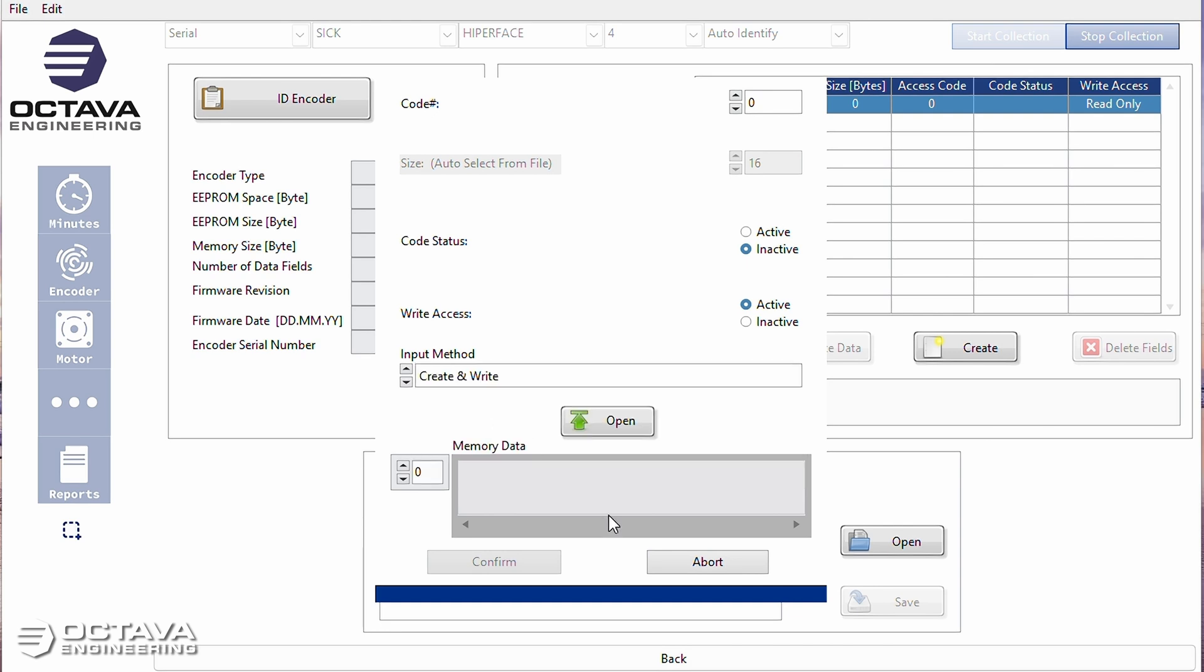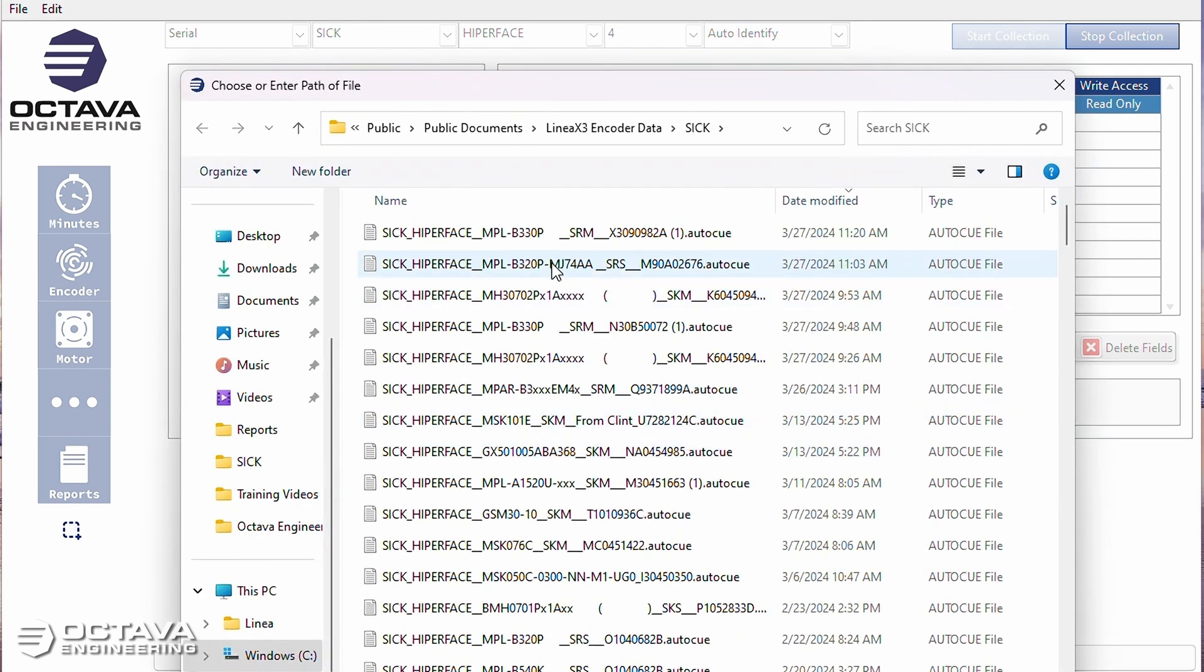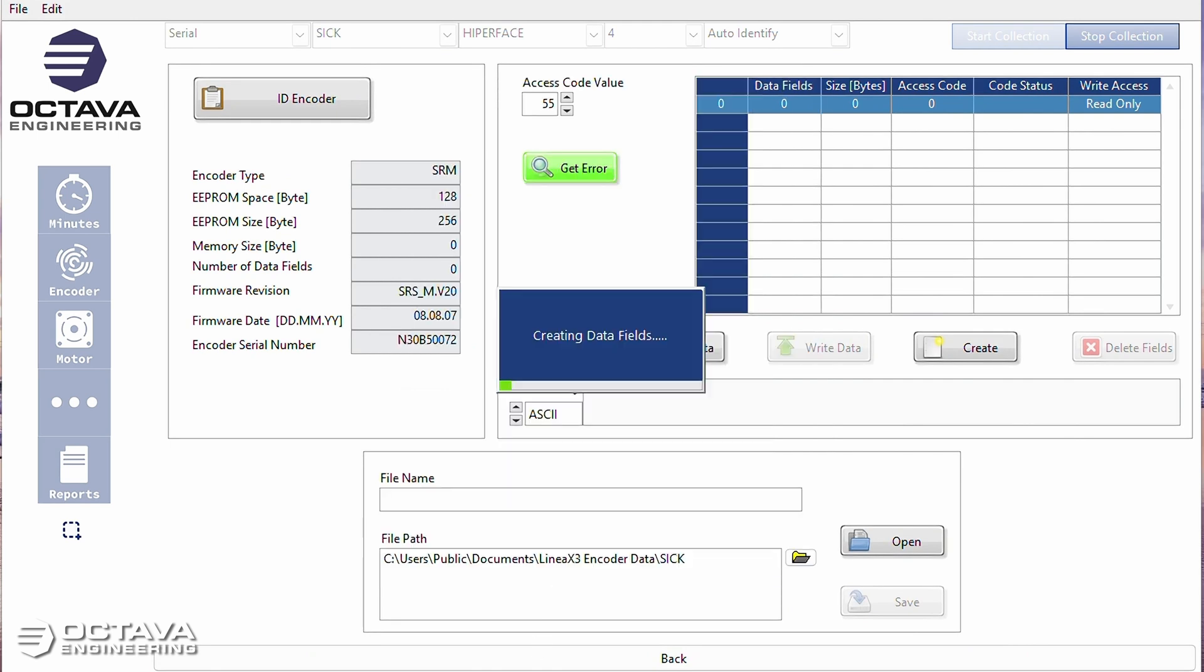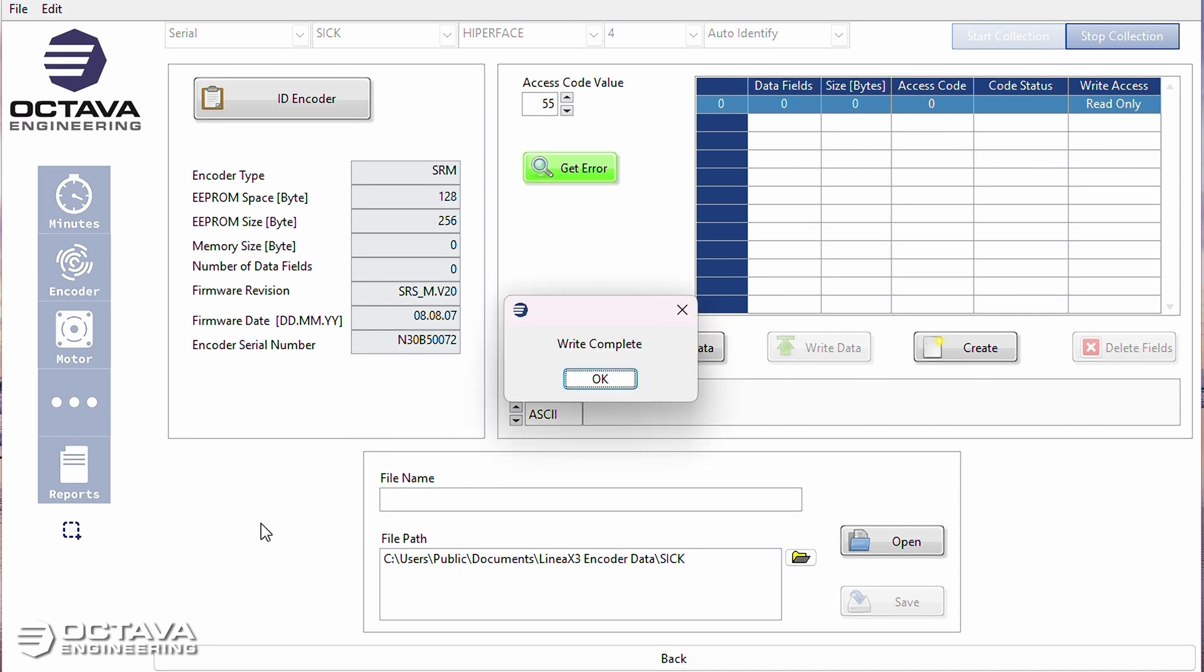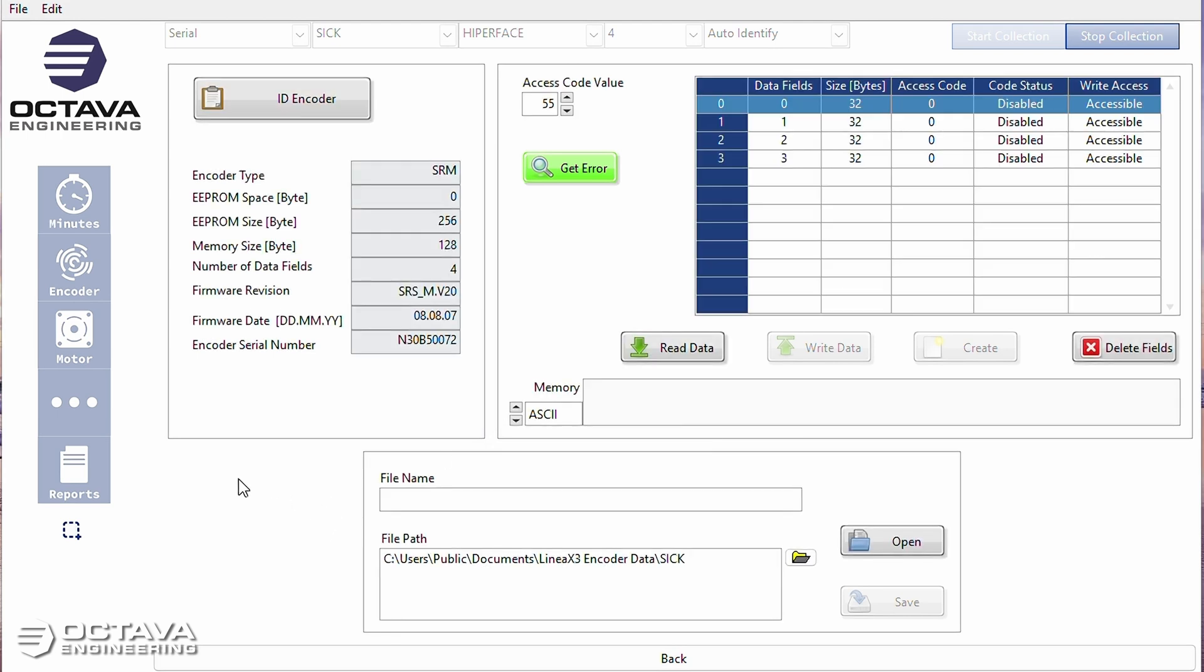So I can take the memory file from that bad encoder right here, write it to the good encoder, and then install it under the motor and perform my alignment like we did in the previous video.